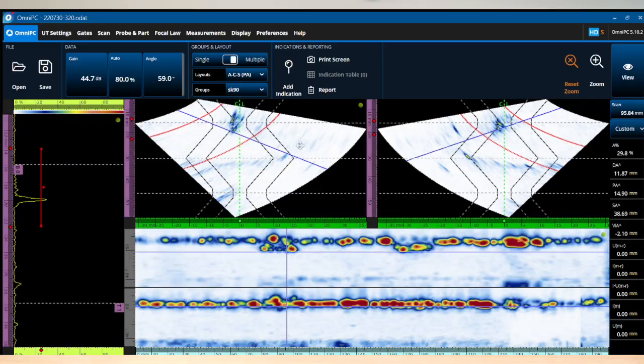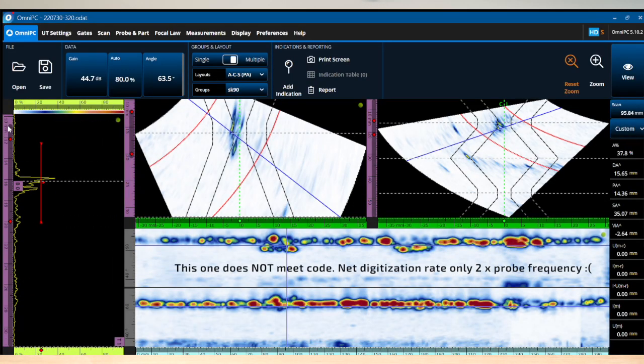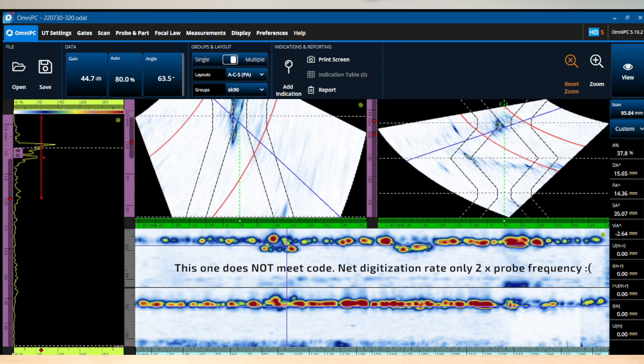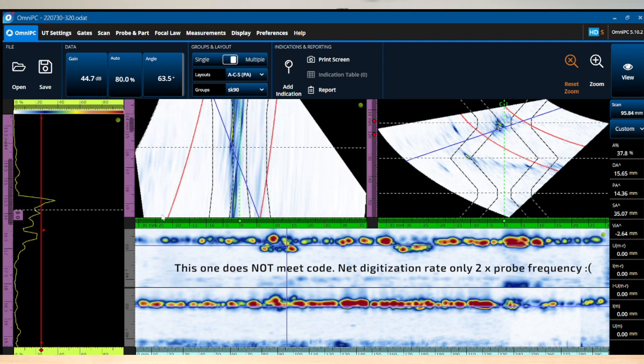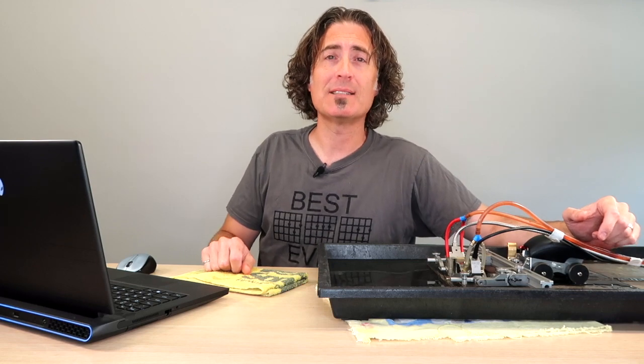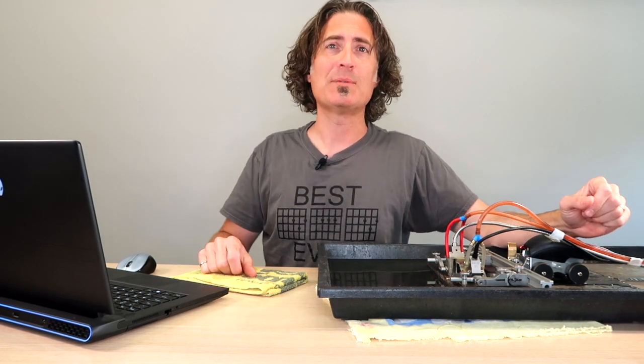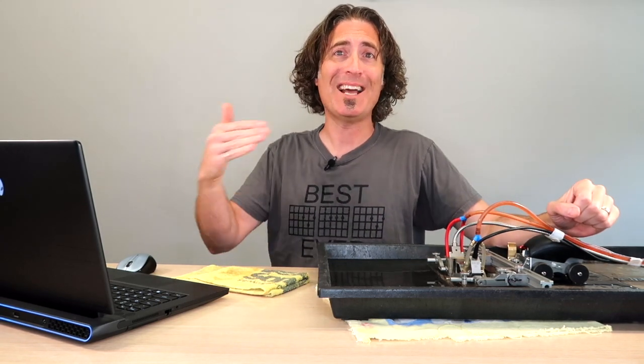Now let's take a look at the low resolution one. When we zoom into the A scan here, you can see it does look significantly more chunky. This is what they're trying to protect you against. They want you to be able to see those little ups and downs. The amplitudes are still all good. We just don't have that resolution along the A scan. And we need that to do things like tip diffraction sizing for the height of flaws.